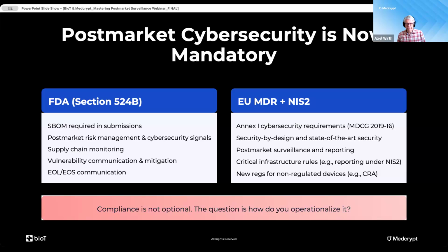FDA most recently aligned their cybersecurity requirements with Section 524B of the FD&C Act, which includes SBOM requirements, SBOM to be included in the submission to FDA, but also your commitment to post-market risk management, monitoring of cybersecurity signals, monitoring of your supply chain, and then mitigating and communicating identified vulnerabilities. And then lastly, also make sure you stay on top of your software components, end of life and end of support, and that you're in the position that you can proactively communicate that to your customers.